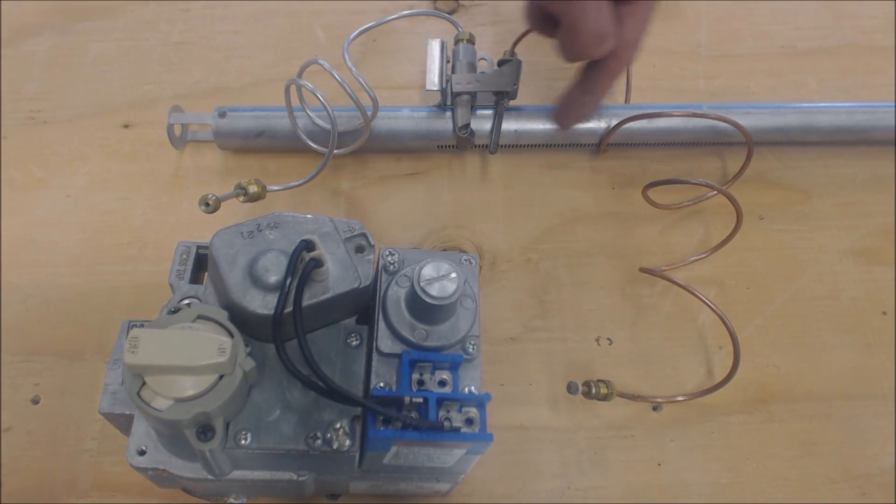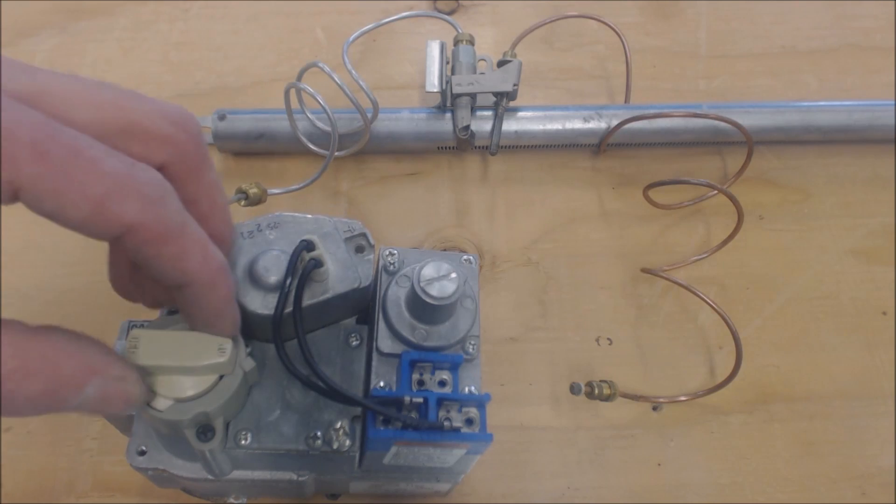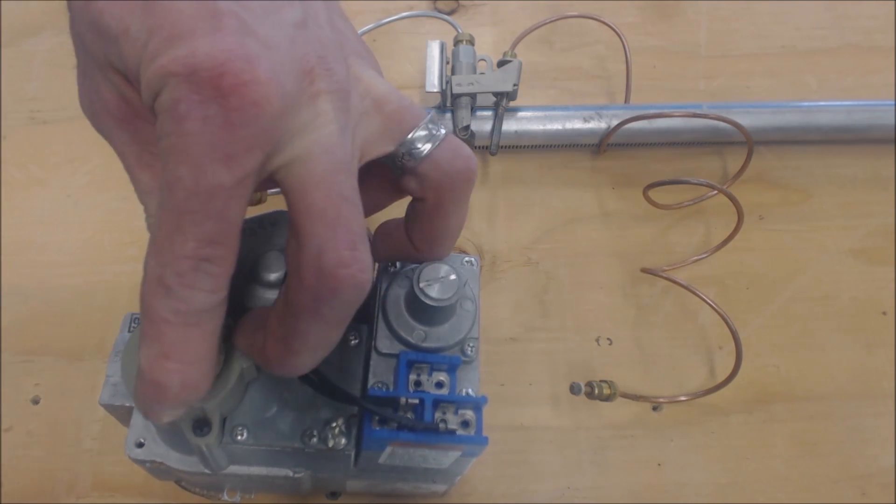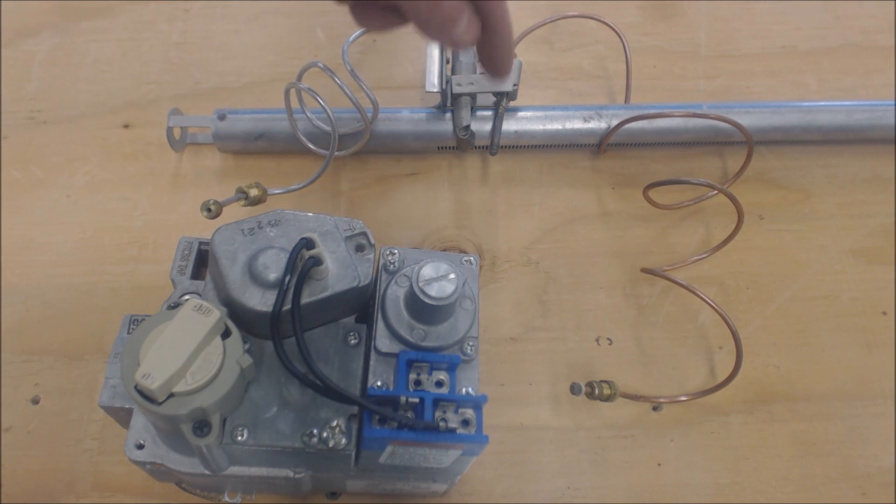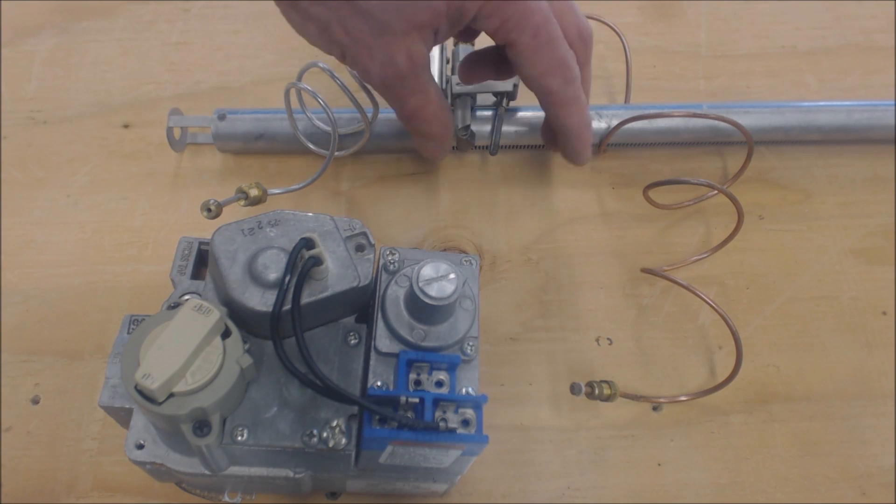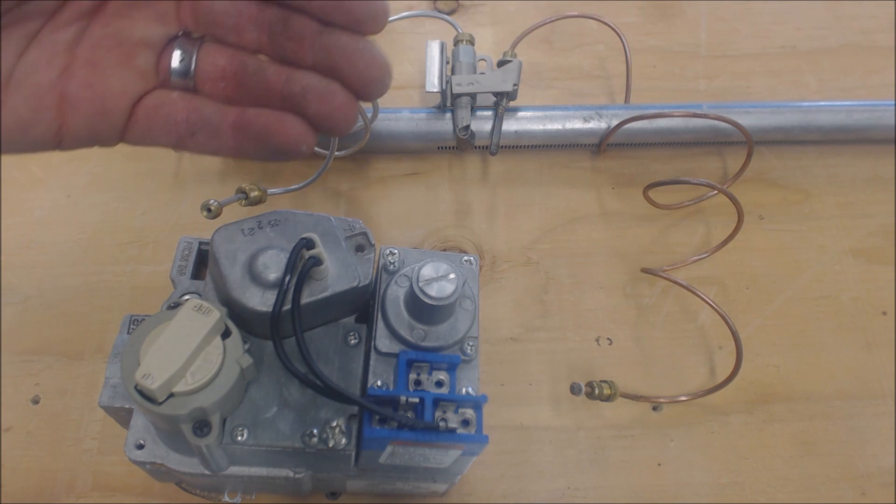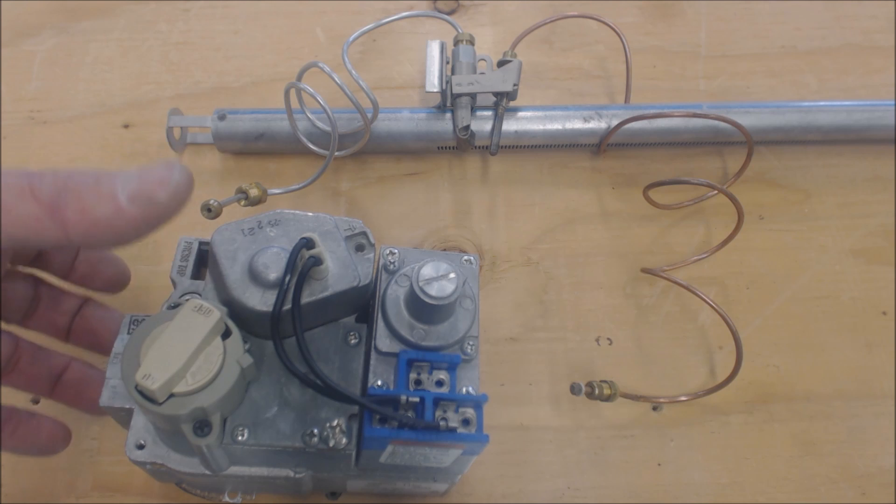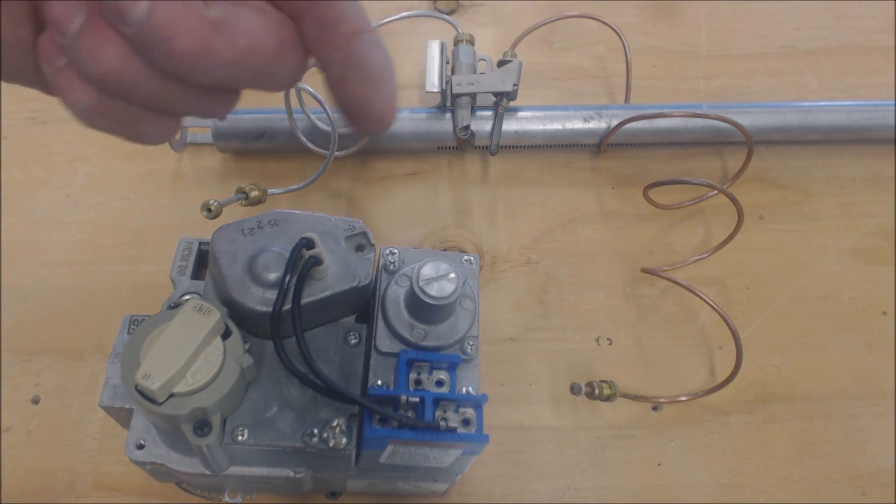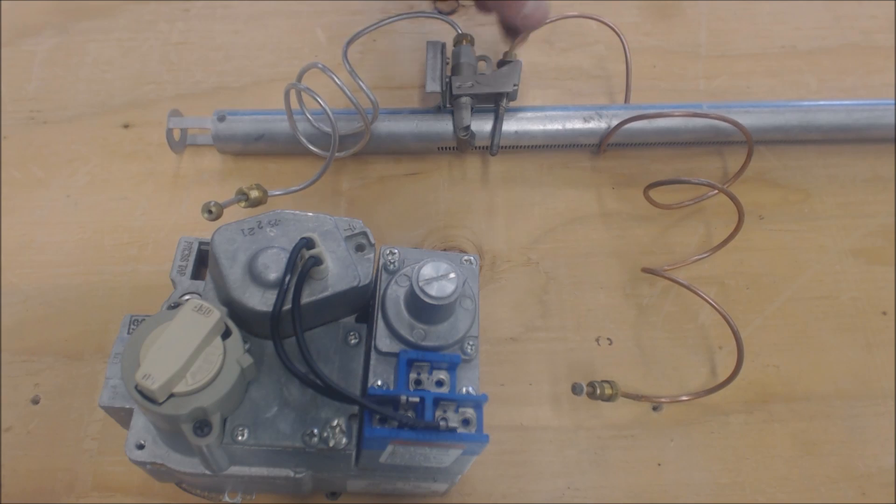As far as the pilot goes, you're holding this button down, allowing gas to flow through and lighting it. Any time you let up on this after a minute, two minutes, three minutes, the flame ends up going out. That has to do with either the thermocouple or inside the combination gas valve there's a solenoid.